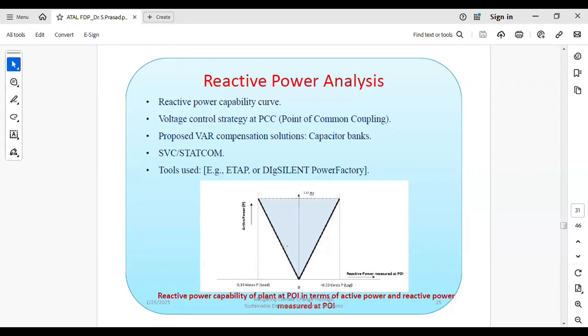So this is one of the most important tasks performed by the consulting engineer: to verify whether we are able to maintain 0.95 lag and lead at the point of interconnection in those two situations. So how much reactive power support you have to provide at the point of connection. This test is conducted using ETAP software or DIgSILENT PowerFactory, and based on it you give a solution to the EPC contractor, that you can go for SVC or STATCOM.